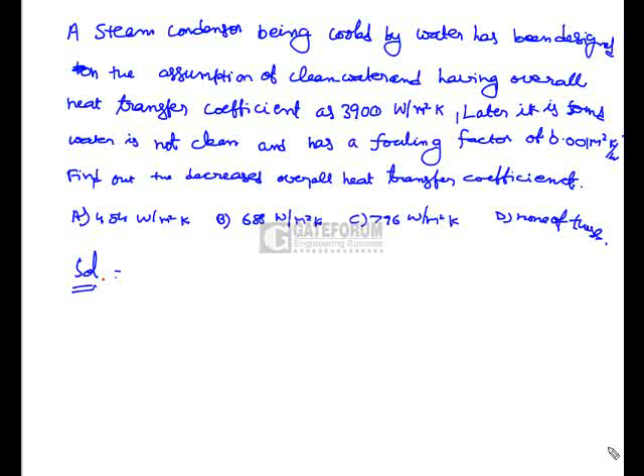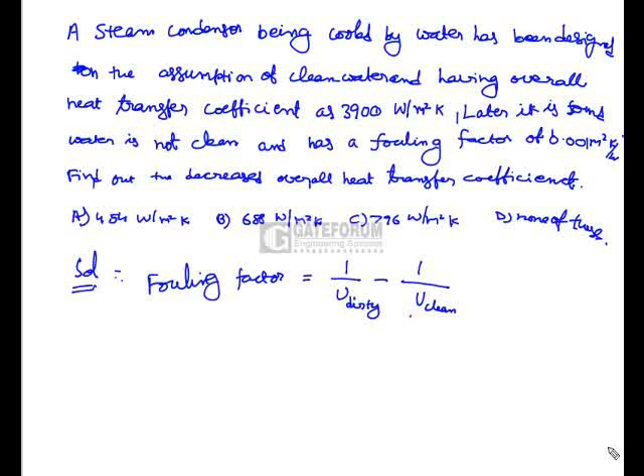Coming to the solution, the formula for fouling factor is: fouling factor = 1/U_dirty − 1/U_clean. Here U_dirty represents the heat transfer coefficient decreased due to the dirtiness of the water, and U_clean represents the heat transfer coefficient for clean water.